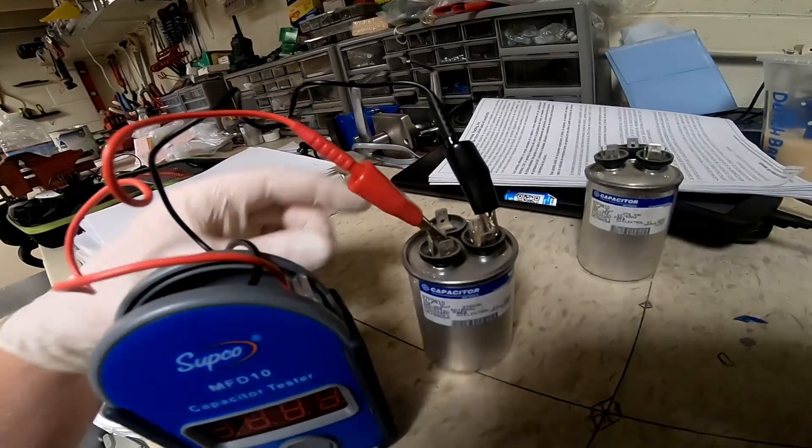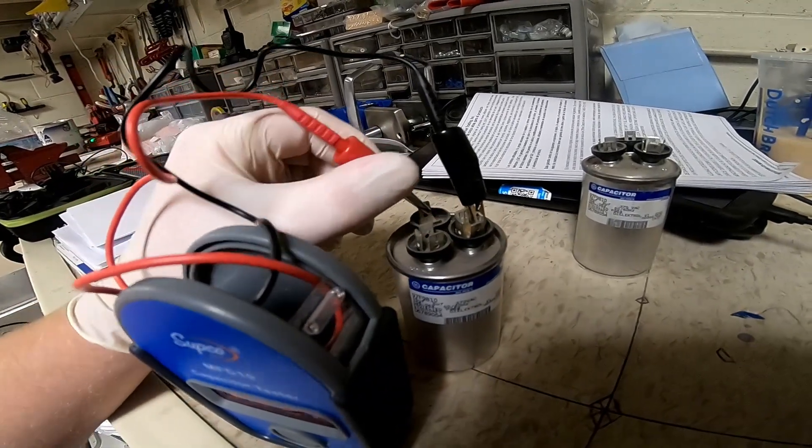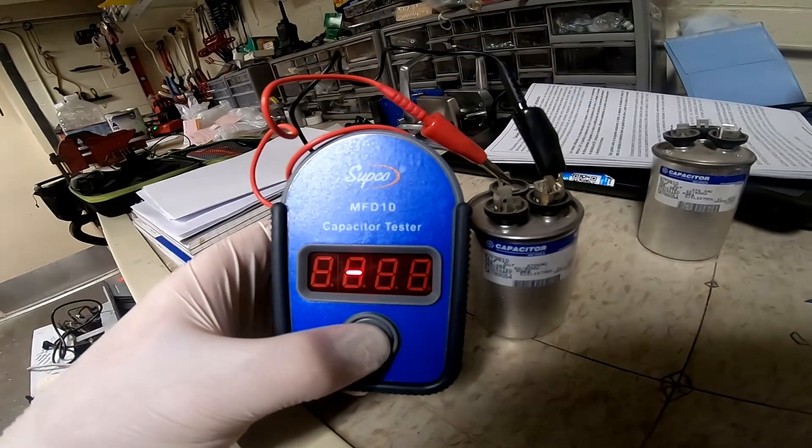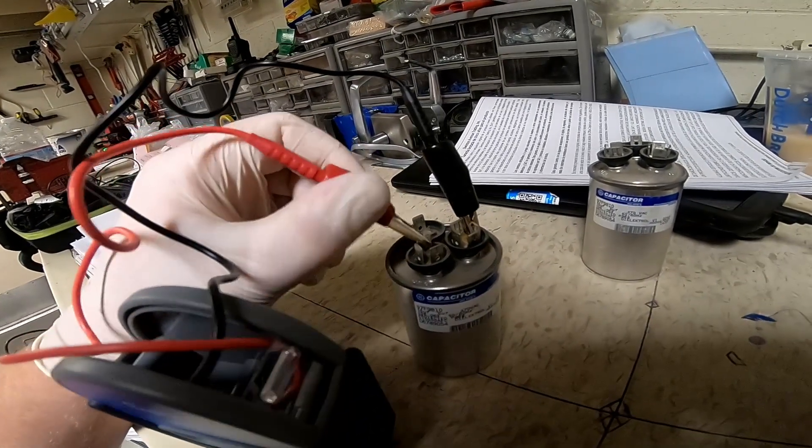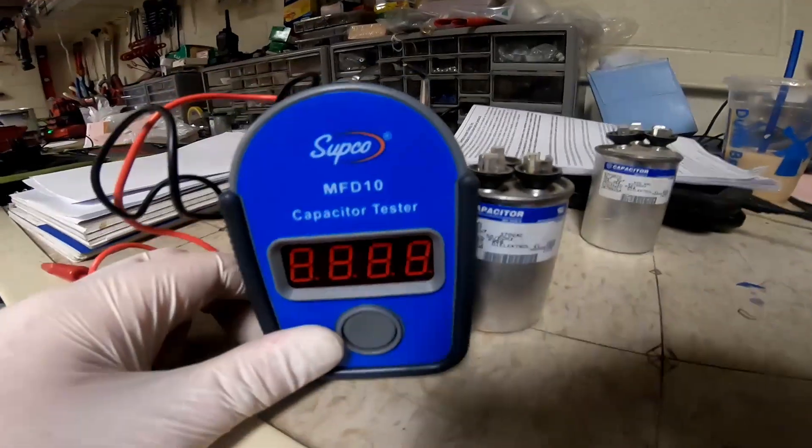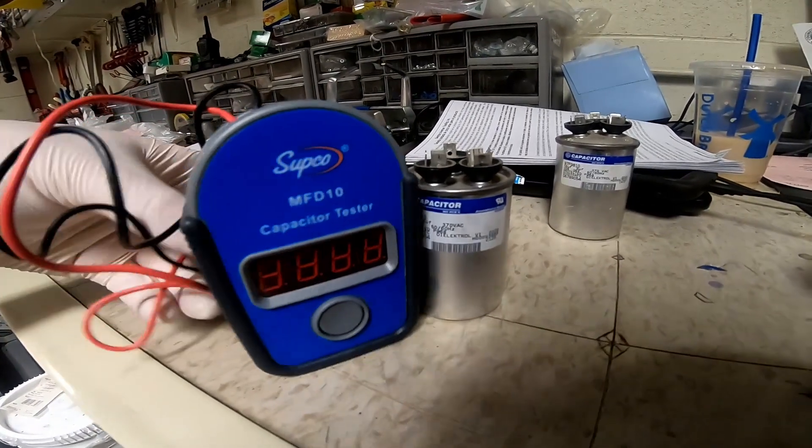And this one should be 5 plus or minus 6 percent, 4.9. That one's good, but the one that fires the compressor is no good.